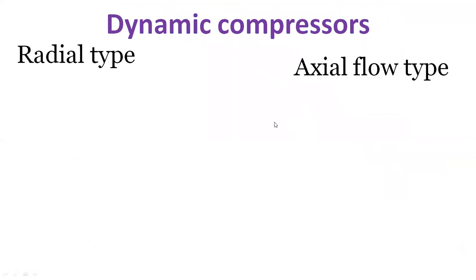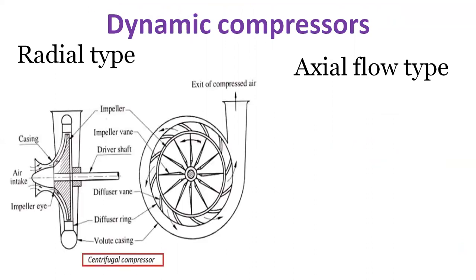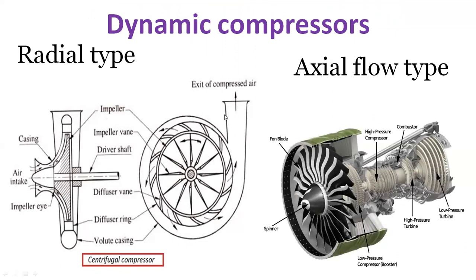Dynamic compressors increase air velocity, which is then converted to increased pressure at the outlet. They are centrifugal compressors, further divided into radial and axial flow types. Unlike pumps that deal with incompressible liquid, for air, throttling the output increases pressure because it gets compressed. Centrifugal compressors are typically suitable for outputs above 12,000 cubic feet per minute. A radial type takes air in axially and delivers compressed air radially, while the axial flow type acts like a turbine.